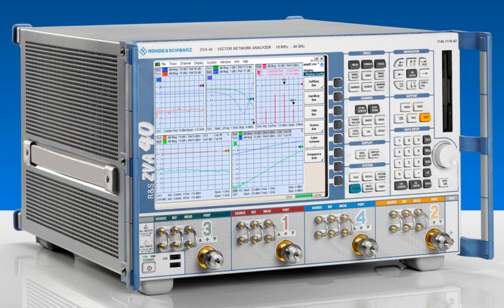Reflection tracking — error resulting from all frequency dependence of test leads, connections, etc. In a typical one-port reflection calibration, the user measures three known standards, usually an open, a short and a known load. From these three measurements, the network analyzer can account for the three errors above. A more complex calibration is a full two-port reflectivity and transmission calibration.